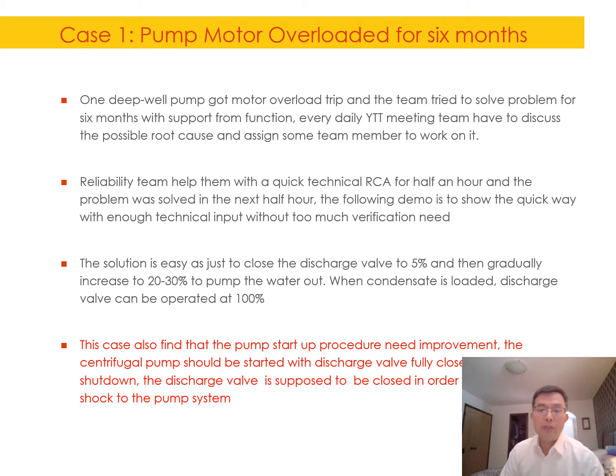We're looking at one case here, a real case I worked on before. We have one deep well pump. The team there worked on this problem for 6 months, on the motor overloading. Every time they tried to start the pump to pump the liquid from the vessel, they got overloading.